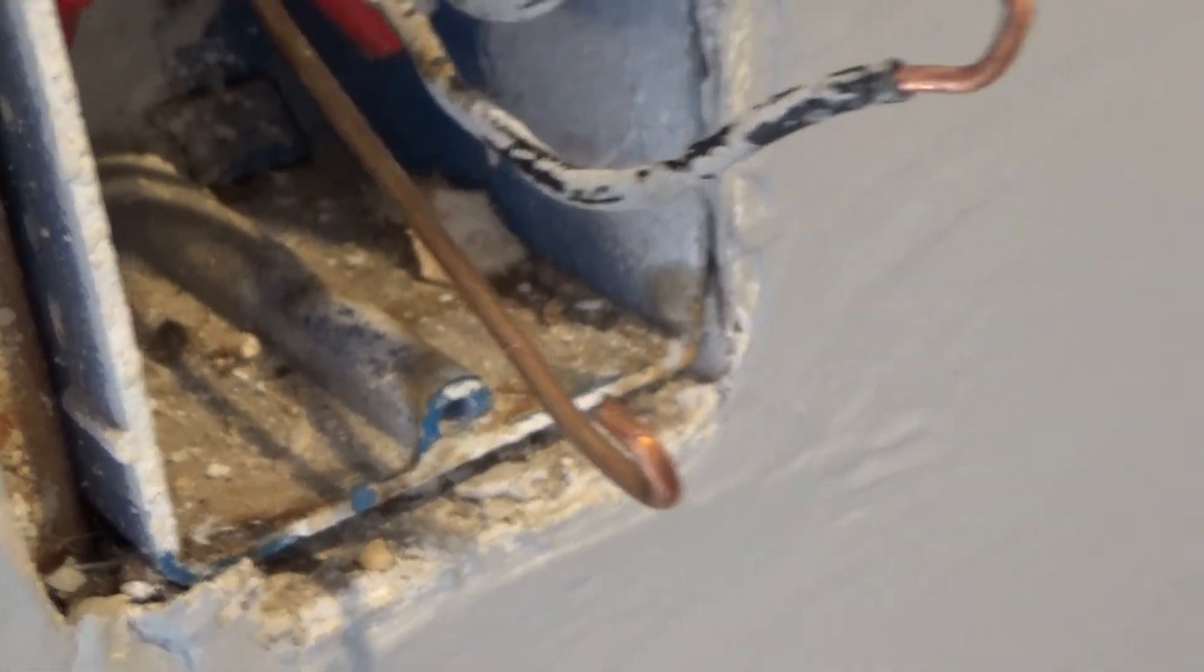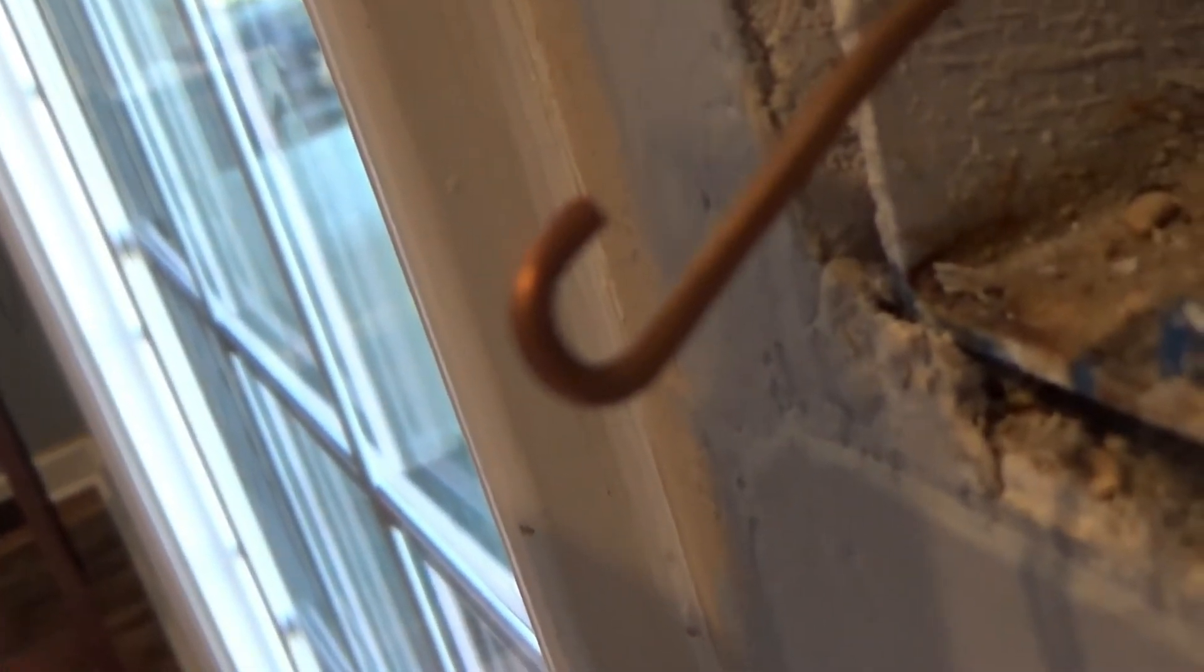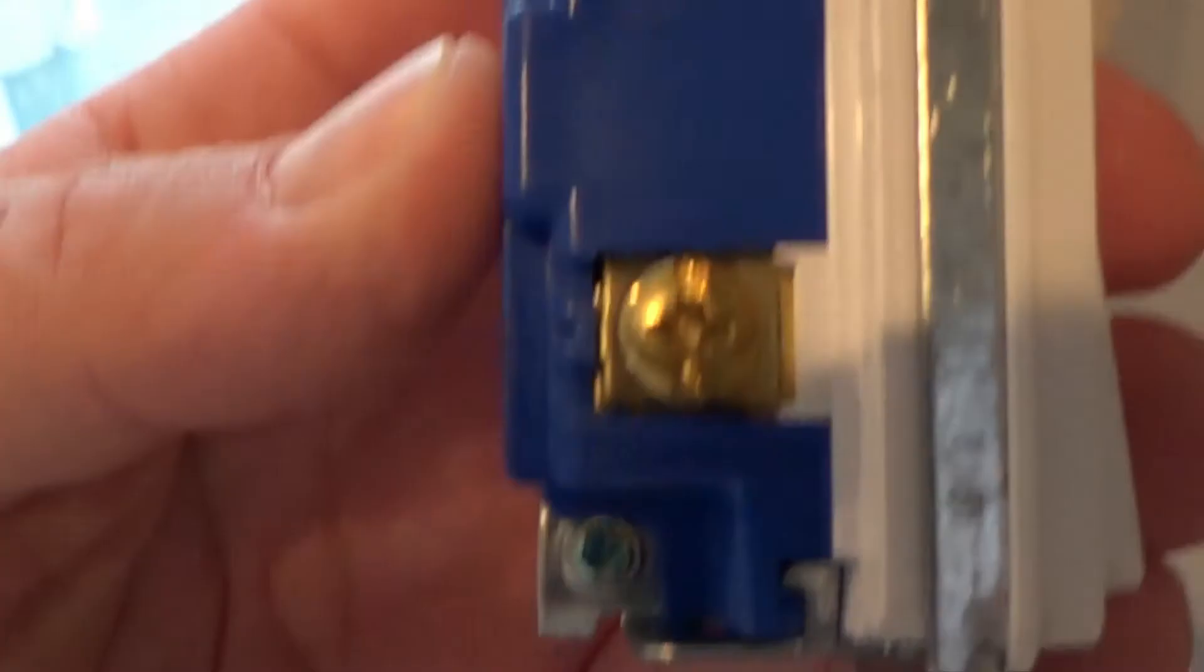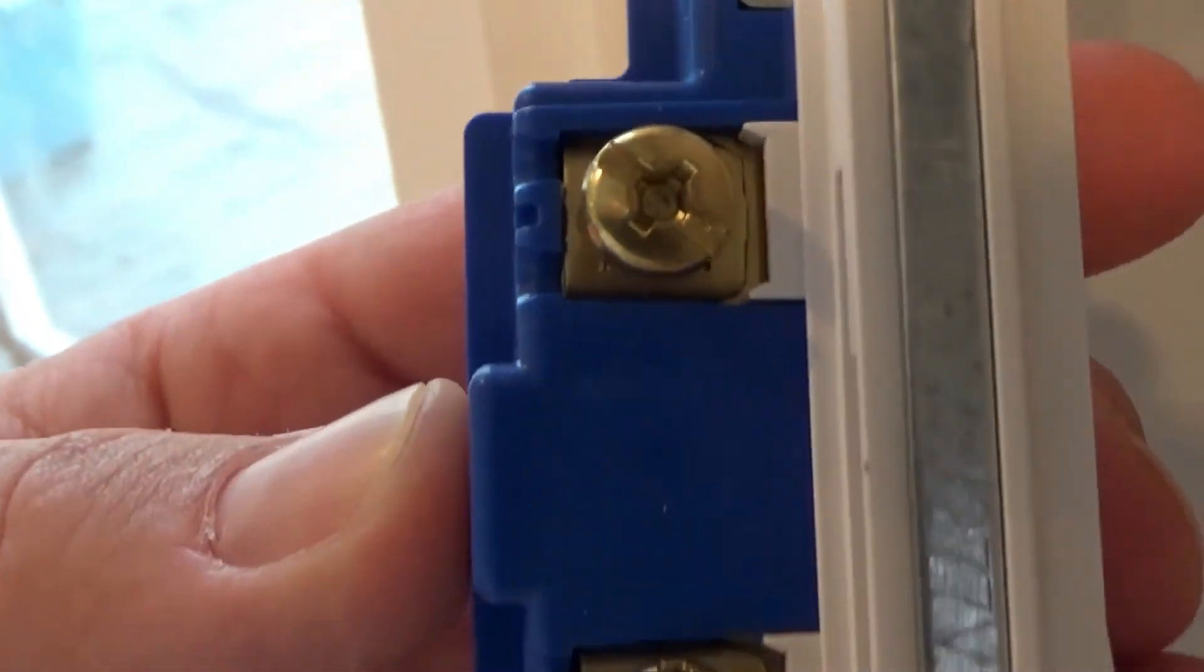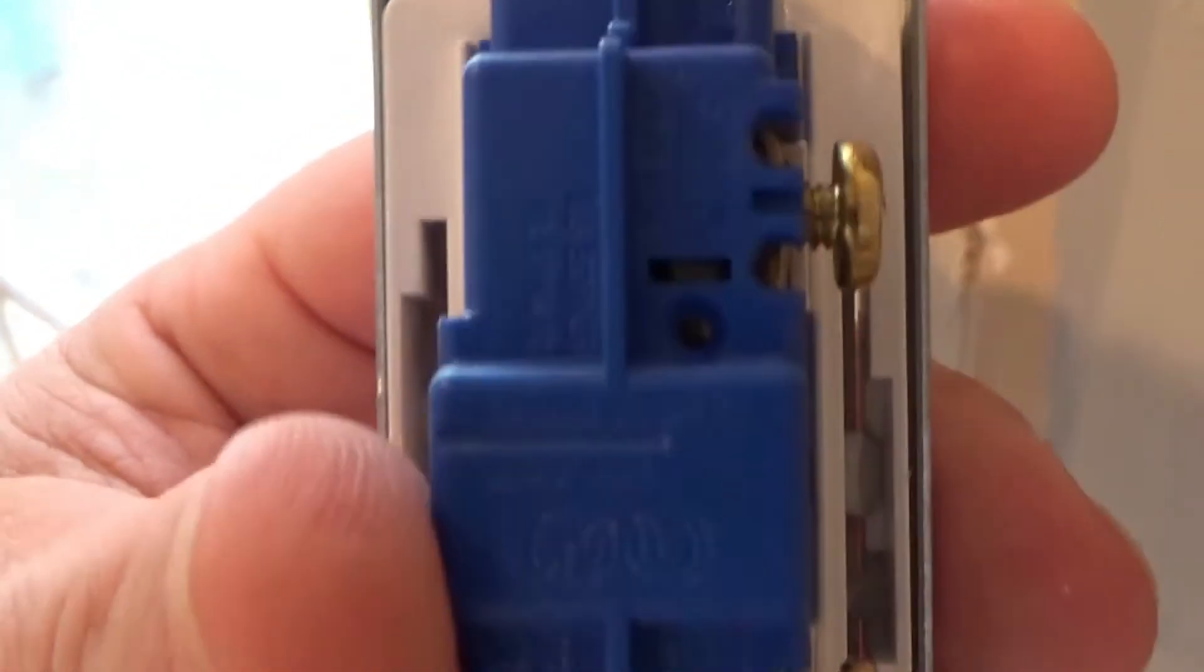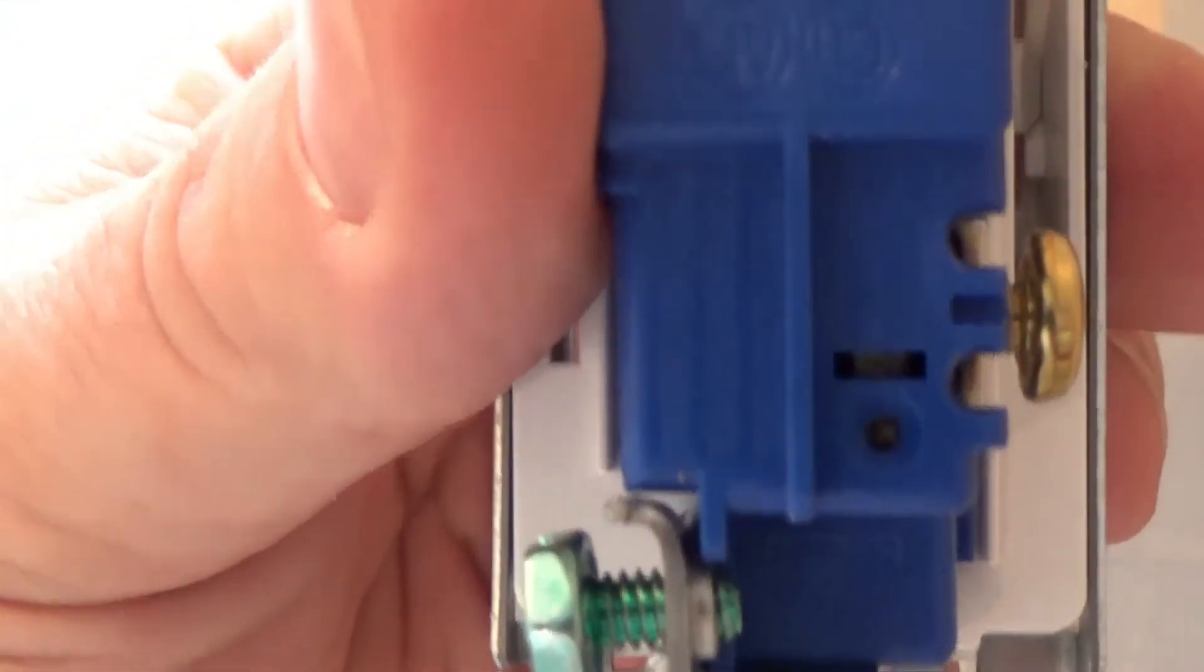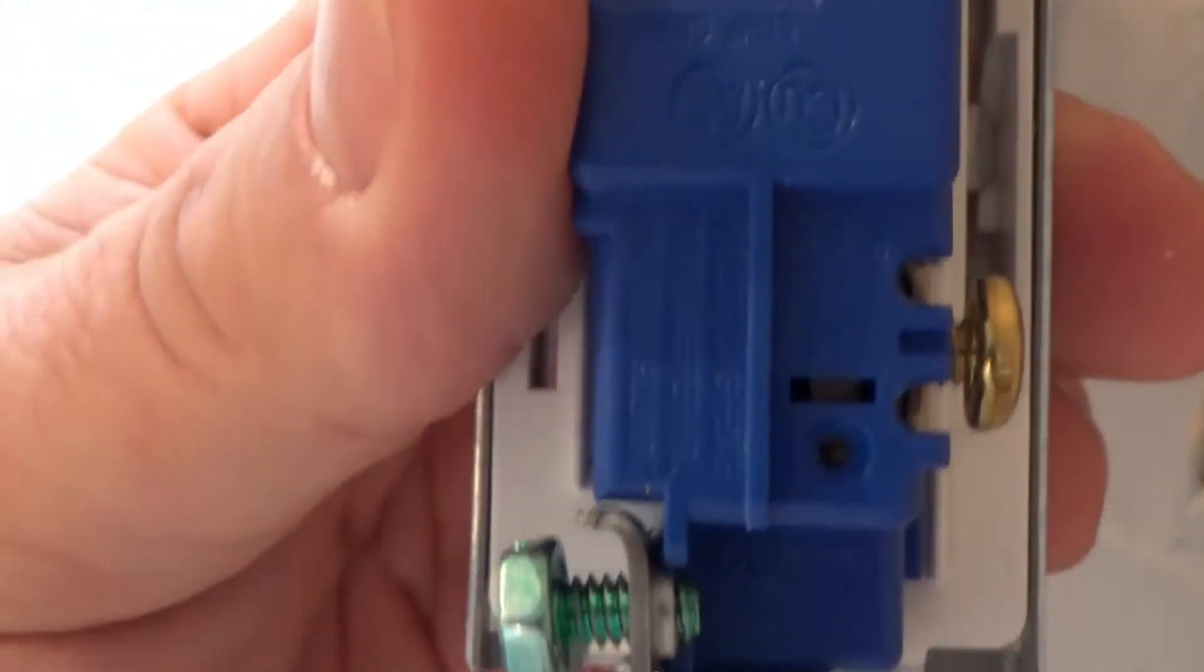When you make your loops, you don't want your loops to go back past the insulation. We always use the screw ends as much as possible. We don't like to use the stab ends unless we have to, because they're not nearly as reliable. So we're ready to put this in.